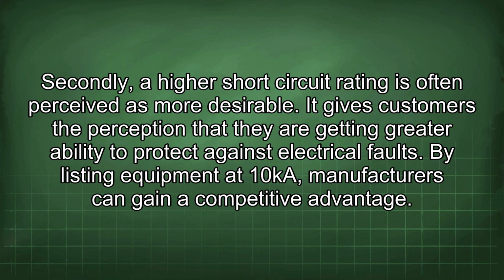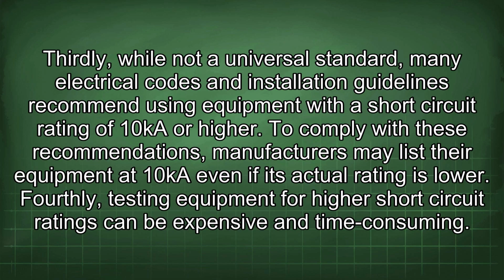Secondly, a higher short-circuit rating is often perceived as more desirable. It gives customers the perception that they are getting greater ability to protect against electrical faults. By listing equipment at 10kA, manufacturers can gain a competitive advantage. Thirdly, while not a universal standard, many electrical codes and installation guidelines recommend using equipment with a short-circuit rating of 10kA or higher.